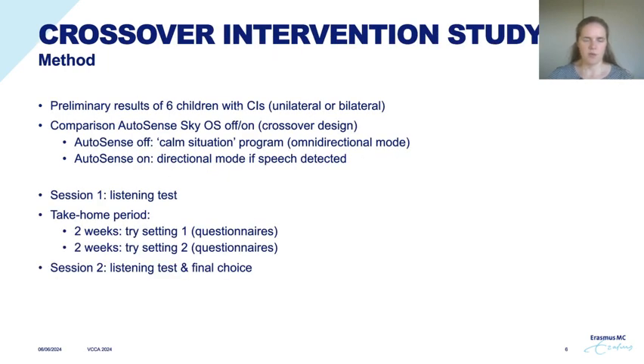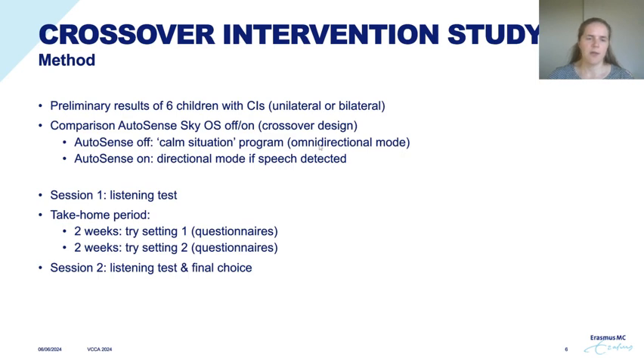I will show today the preliminary results of six children with cochlear implants — they had unilateral or bilateral cochlear implants. We compared a setting with AutoSense on and off. When AutoSense was switched off, the hearing device was always in the calm situation program, which means it had the omnidirectional microphone setting. When AutoSense was switched on, it switched to directional microphone mode if speech was detected.